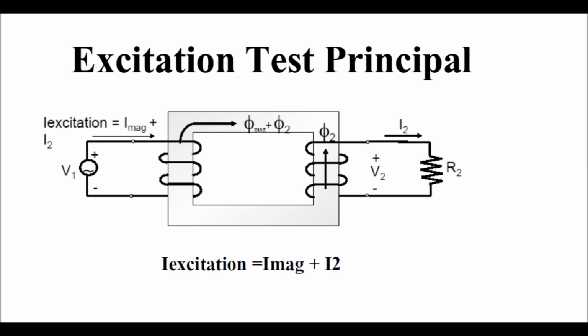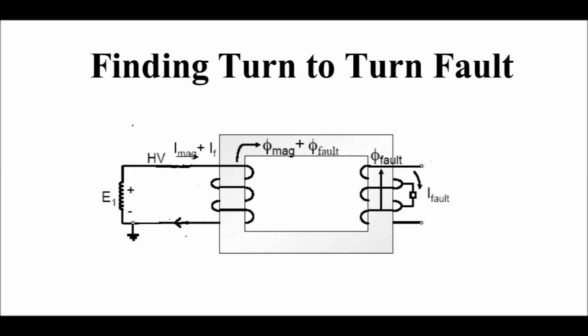Now whenever a load is connected, more current will be drawn on the primary side. In no load, there is only magnetization current. Therefore, with the transformer at no load, we supply a single phase supply to the primary winding or either side of the winding. It will help to detect an interturn fault in the secondary side winding or in the primary side winding. Here the circuit diagram has been shown for finding an interturn fault during the magnetization current test. Now single phase supply E1 voltage has been applied to the primary side winding. Due to this, only I magnetizing current should flow in the primary side winding. Therefore only phi magnetizing flux should flow in the core.